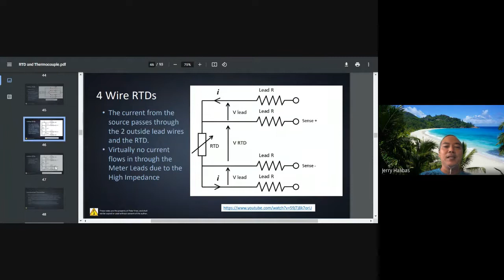Same principle, 4 wires. Okay? So we go now from the RTD sensor. From the sensor, we first put a transmitter. Okay? So if it is a transmitter, it is called an analog output. Though a temperature sensor or an RTD sensor is analog already, its output is resistance.